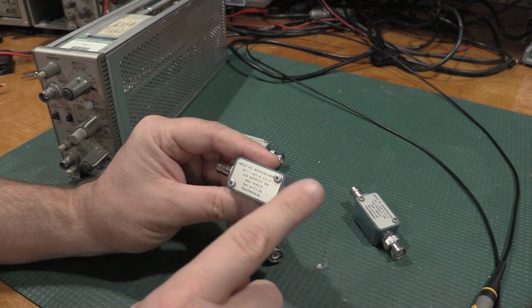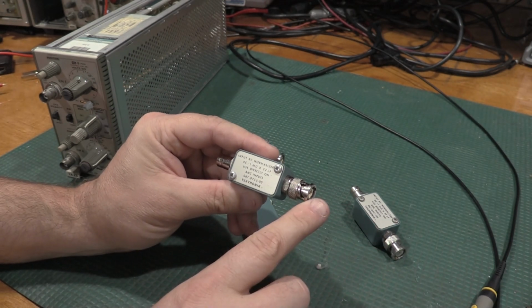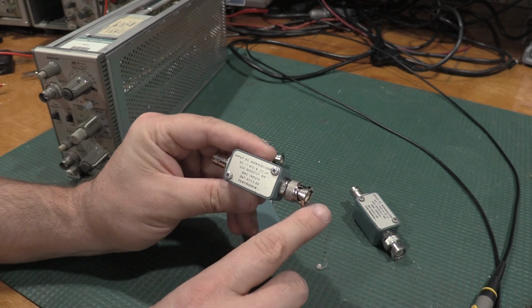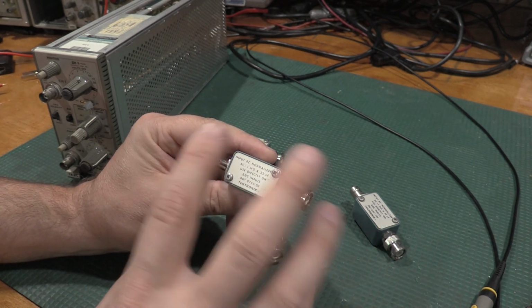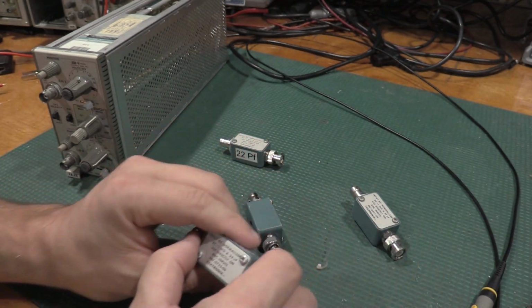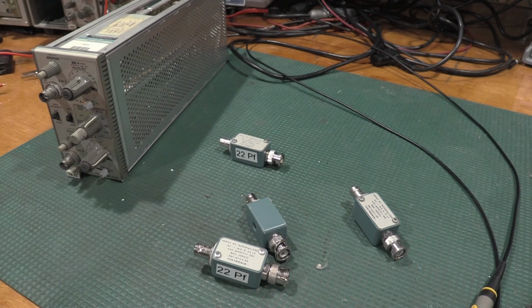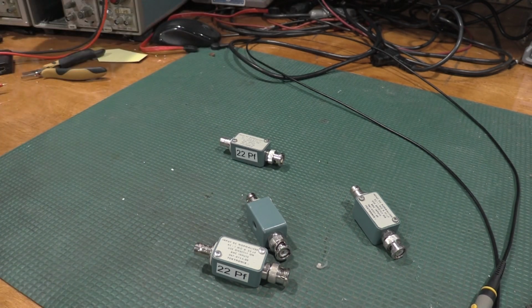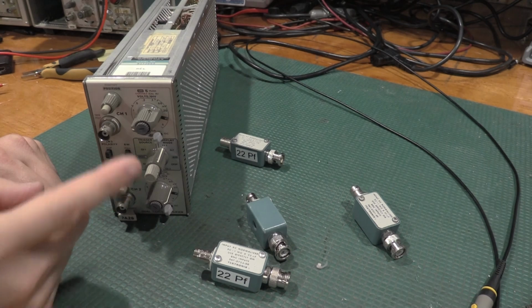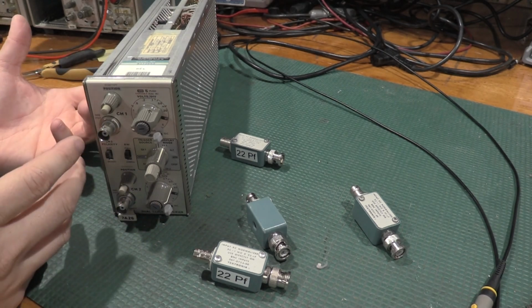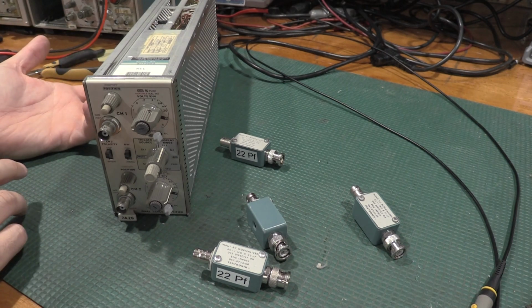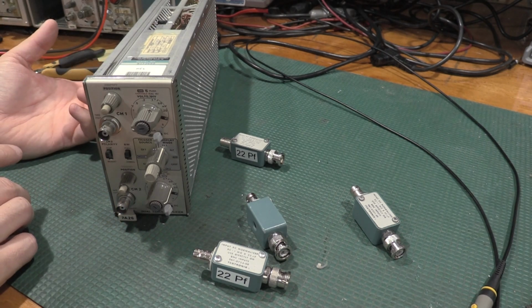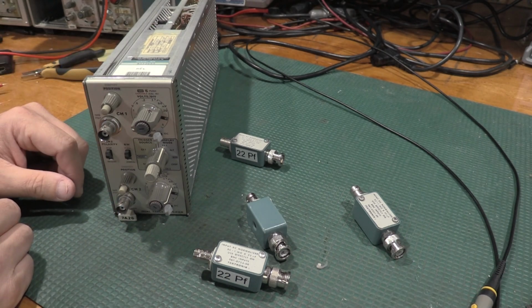And then sometimes you'll even have a 50 megohm, or a 50 ohm, not 50 megohm, 50 ohm terminator on the front of this, depending on what you're doing. There are a couple of adjustments that need 50 ohm. Now, if you're doing a 400 series scope, or you're doing something that you'd like better than 50 ohm, or that you're going to primarily use in a 50 ohm system, what you can do is do the alignment not with a normalizer, but with a 50 ohm terminator. When you do that, you just have to know that you've skewed the alignment, not in a bad way, but towards 50 ohm as opposed to what would be a nominal input capacitance.